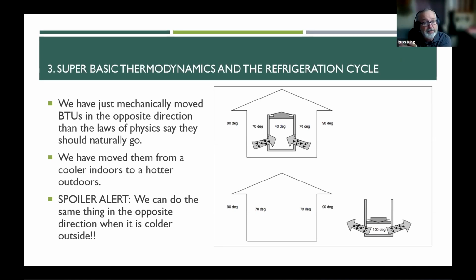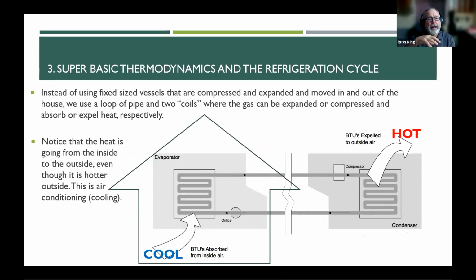So all the stuff I've been explaining before is air conditioning, removing BTUs from a house. Now we can do the exact same thing going the opposite direction. We can absorb heat from the outside and bring it to the inside. But we don't have containers that do this. Our air conditioner isn't a bunch of containers going in and out, in and out. It's actually a pipe. It's a continuous stream of refrigerant. And instead of having a container that expands, there's a spot in that cycle where the refrigerant expands, and then it moves along the pipe and gets squeezed out. That's sort of the evolution of the refrigerant cycle, to contain everything inside a closed loop. In part of that loop it expands, and in part of that loop it's compressed. So think of it as a whole bunch of teeny tiny, microscopic containers going through this cycle.